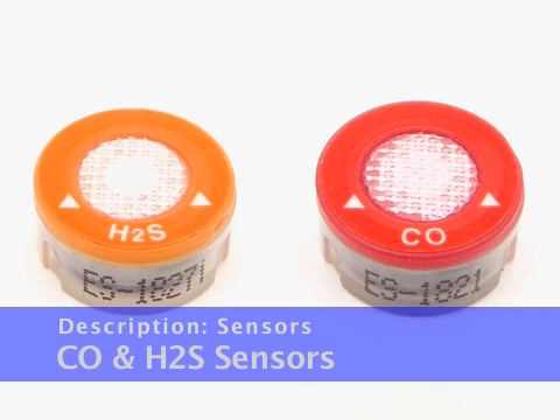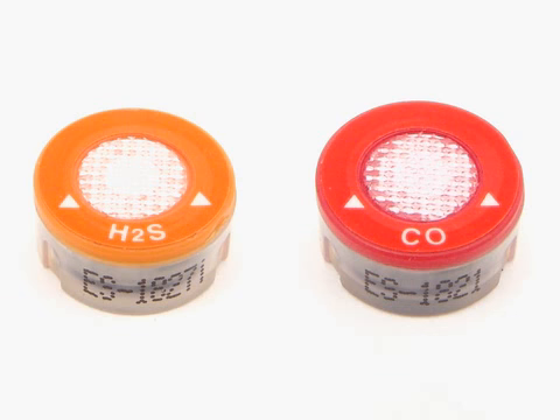The carbon monoxide and hydrogen sulfide sensors are electrochemical sensors that consist of two precious metal electrodes in an acid electrolyte. A gas-permeable membrane covers the sensor face and allows gas to diffuse into the electrolyte. The gas reacts in the sensor and produces a current proportional to the concentration of the target gas. The current is amplified by the GX-2009 circuitry, converted to a measurement of gas concentration, and displayed on the LCD.